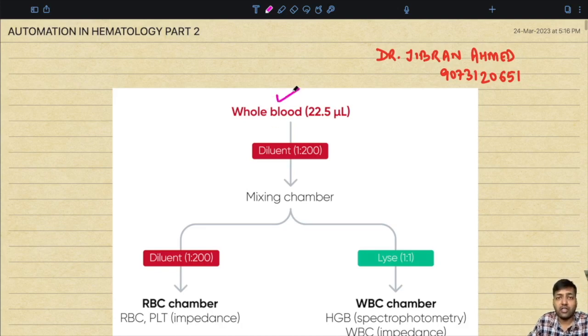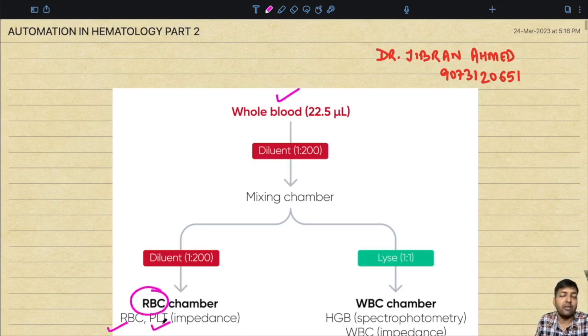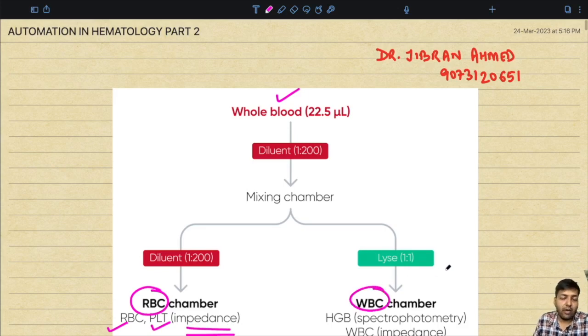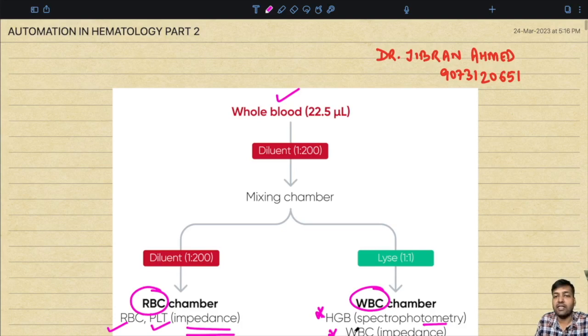You have already seen this particular chart. There are two mixing chambers. In the RBC chamber we do the RBC and platelet count — all those parameters are evaluated there using the impedance method. In the WBC chamber, the RBCs are lysed, and we measure hemoglobin by spectrophotometry and the WBC count along with the differential leukocyte count by the impedance method.